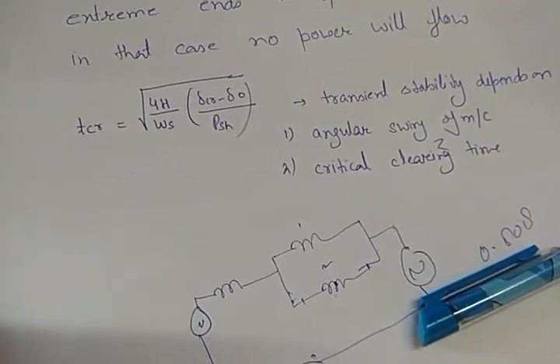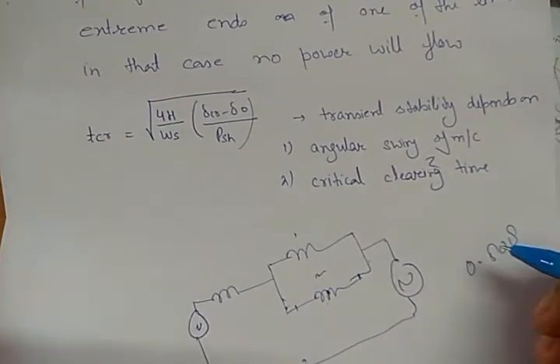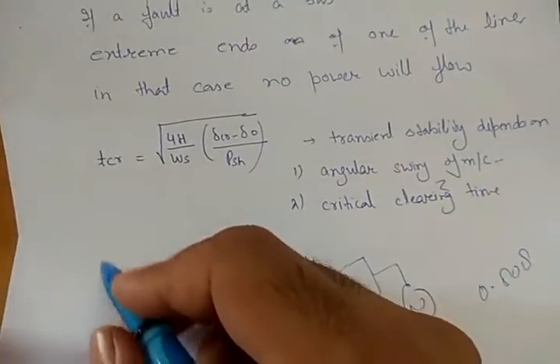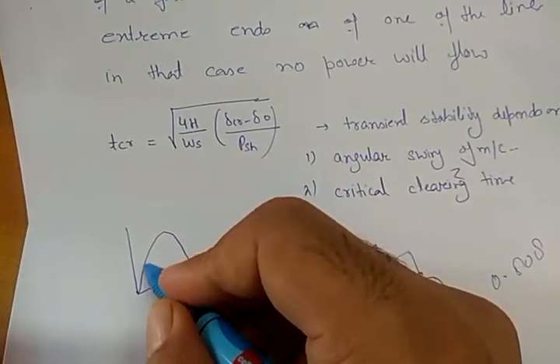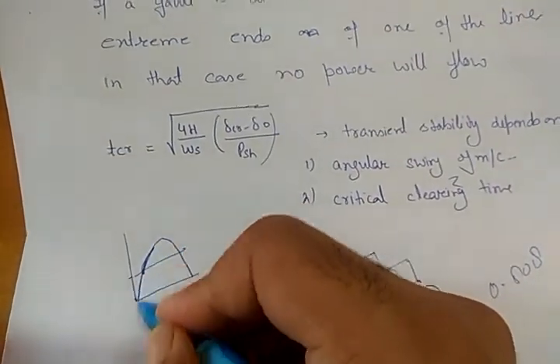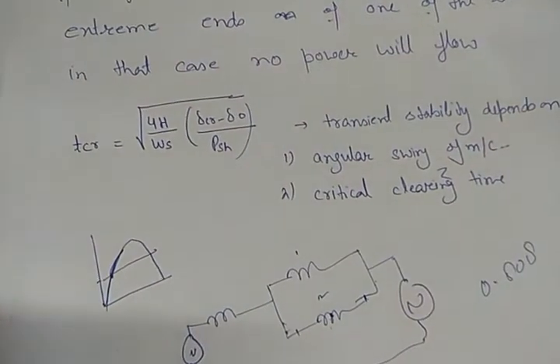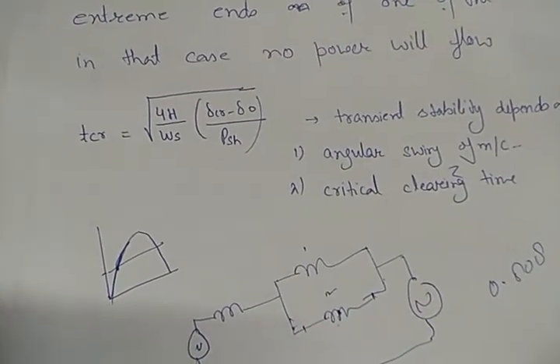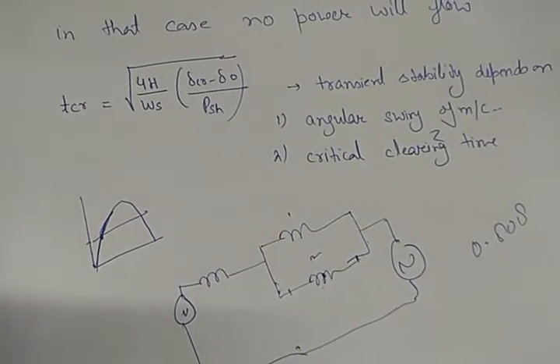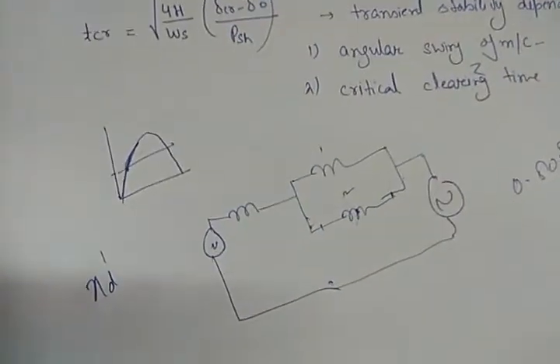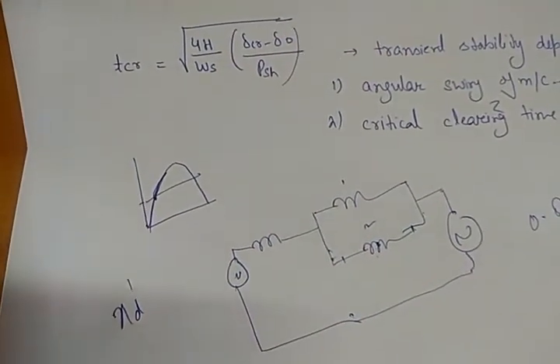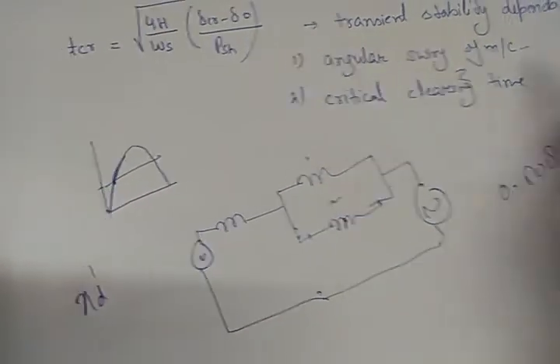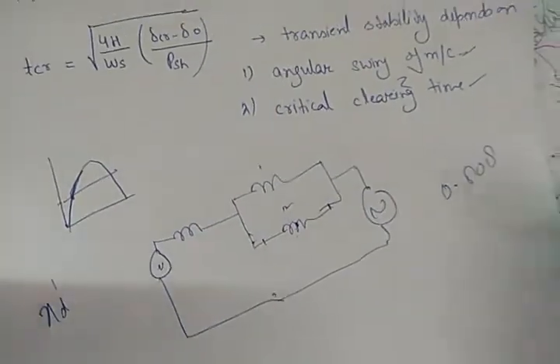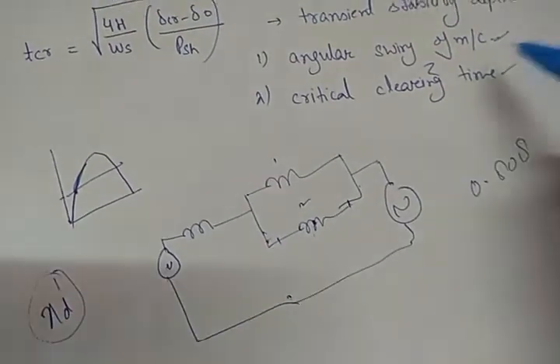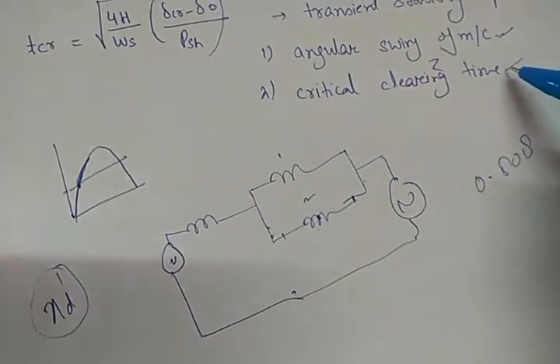But we know transient stability depends upon certain factors like the angular swing of the machine, which means how much delta will increase. If it was initially operating at this point, this is the angular swing: how much delta will increase. So transient stability depends upon the angular swing of the machine and the critical clearing time. Both the H constant and the transient reactance of the generator, which we denote by Xd dash, will have a direct effect on both these factors, the swing of the machine and the critical clearing time.